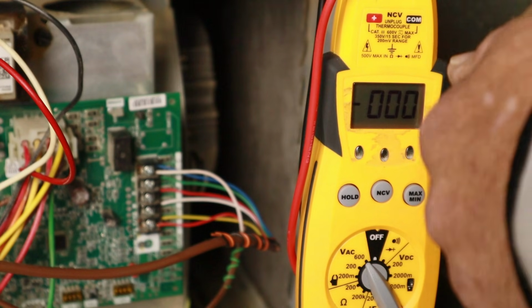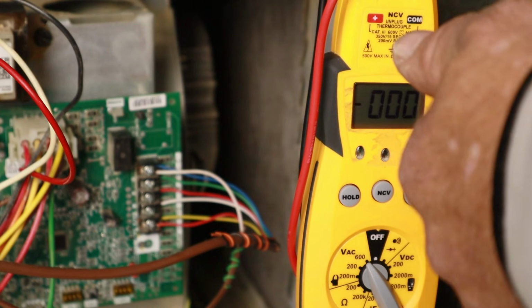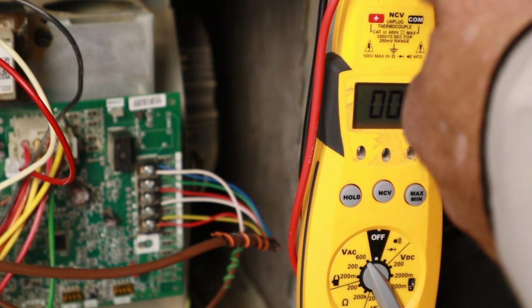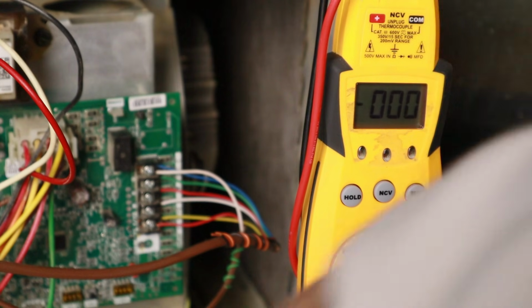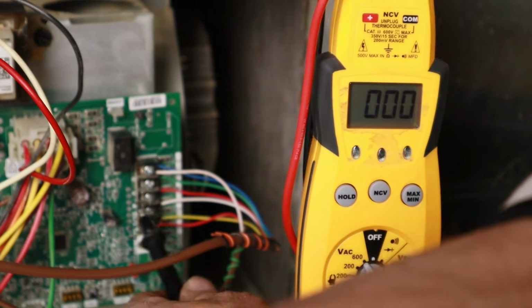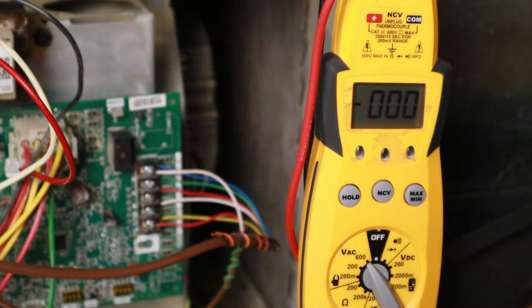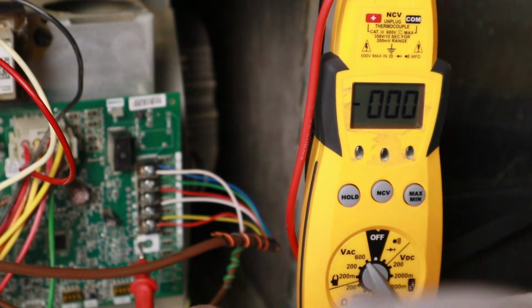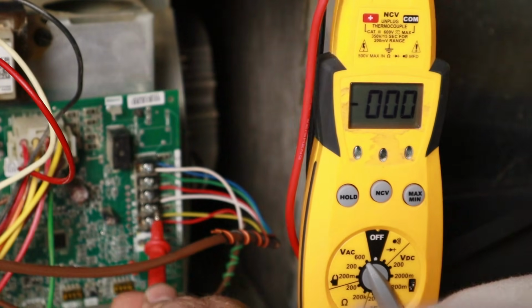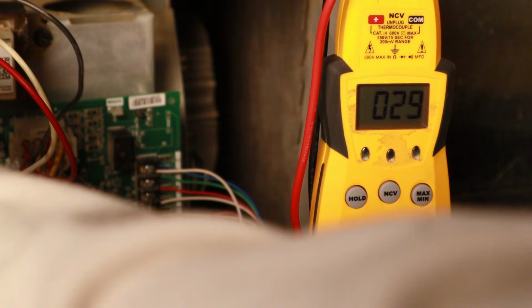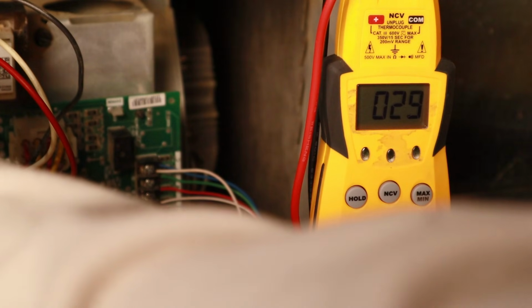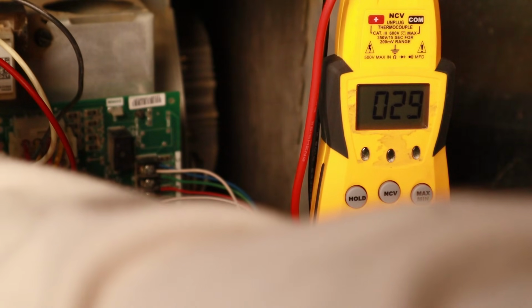The thermostat is going to close a connection between R and W, and that 24 or 29 volts, whatever we're reading, is going to come back onto this W wire here on our terminal block on our control board. So if I were to test for 24 volts there right now, you could see I'm reading 29 volts. So that's telling me my thermostat is working properly. It's sending a signal back.